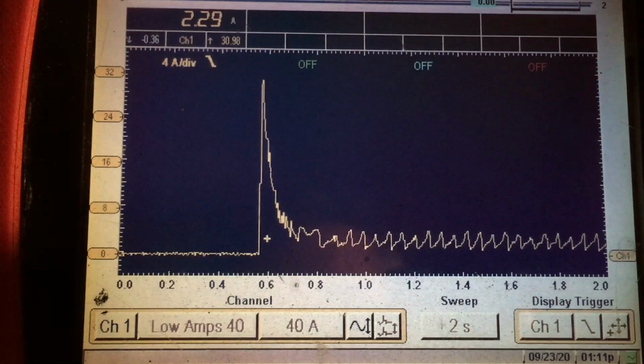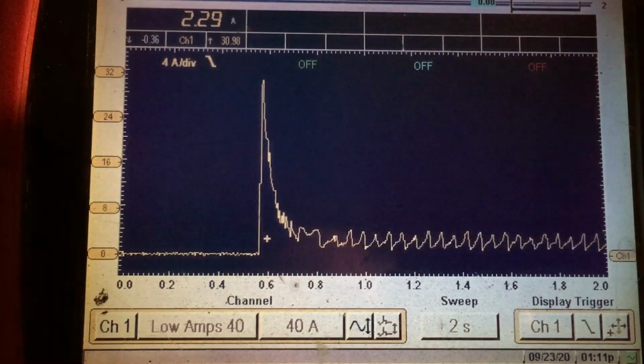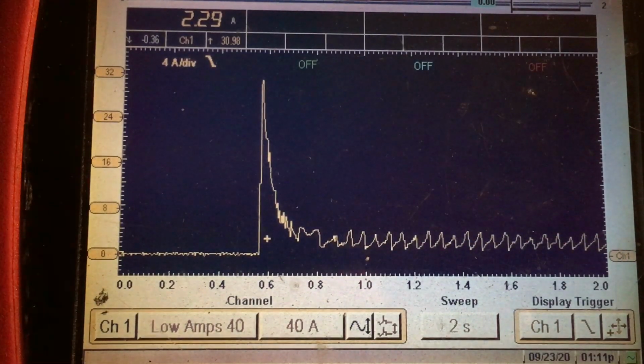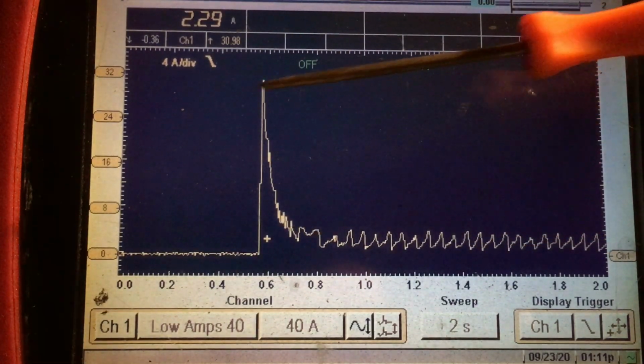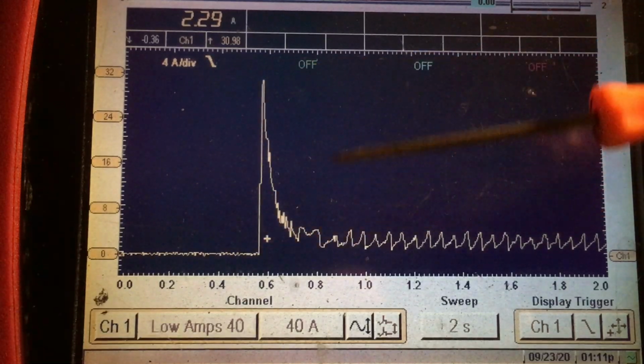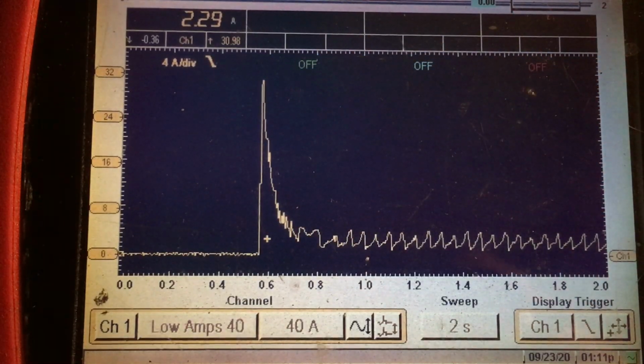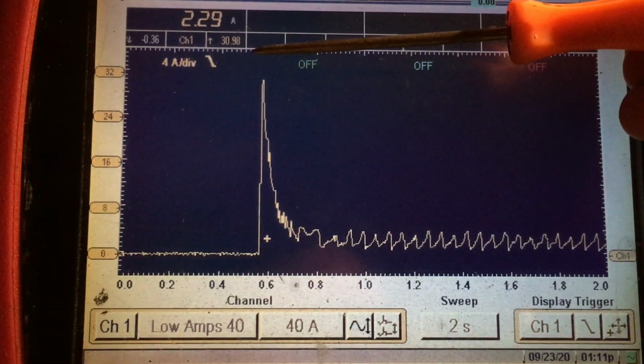You can see that the running current is 2¼ amps as well, so way lower on the running current. As you can imagine, if it's unloaded, it's not going to be drawing a great deal of current. And again, the point I wanted to focus on was this section right here of the inrush current, boys. You can see there's a vertical spike, which is completely normal.